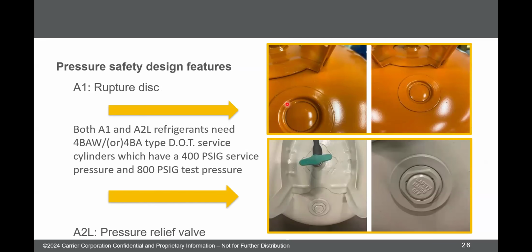Current refrigerant tanks have a pressure relief disc, and the purpose of that relief disc is if the pressure gets too high, this metal is thinner right here in the edge of the disc, so that disc will pop out if the pressure in the tank gets too high, and then it'll relieve the charge that way. As opposed to making everything super strong and tight, including this spot, and then it would have to explode and like shrapnel would go everywhere.